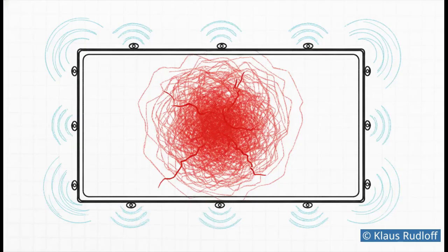The reason those averages trick us so easily is because standard battery management system, or BMS, boundary sensors totally fail to register system-wide warnings in time. Think about the word boundary here. These sensors are often placed at the absolute outer edges of the system. Localized capacity fade is happening deep within the core long before these boundary sensors ever notice a spike high enough to trigger a system-wide alarm. By the time your BMS finally taps you on the shoulder to say there's a problem, the internal damage to the cell lifespan is already done.